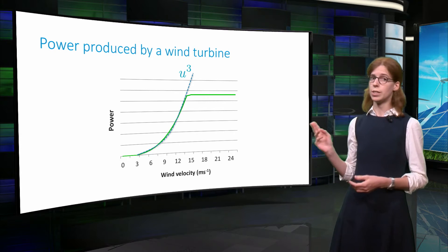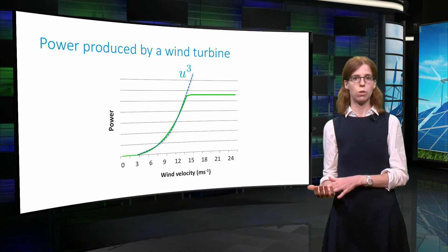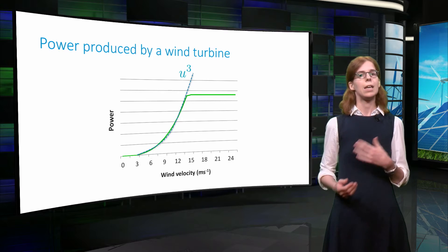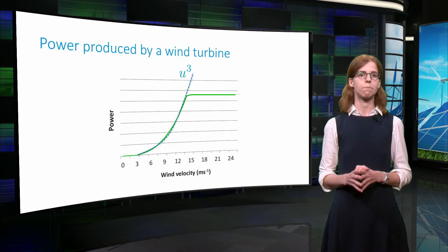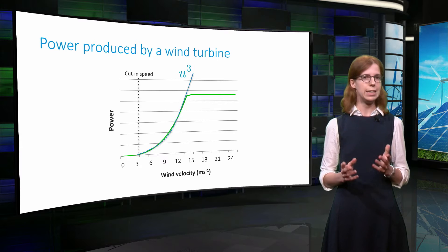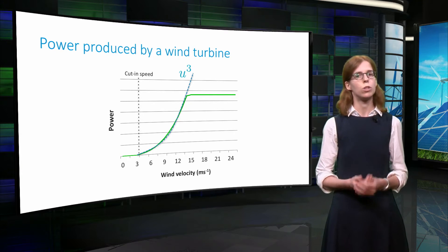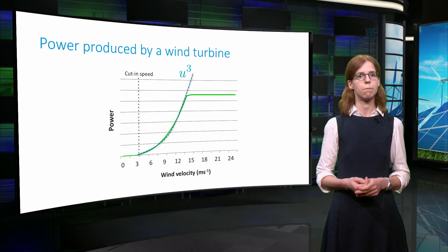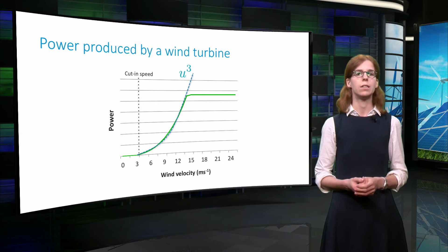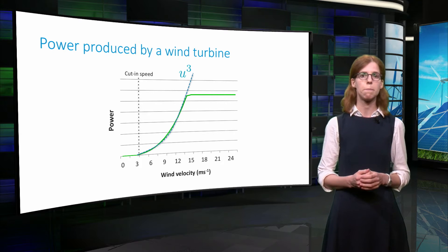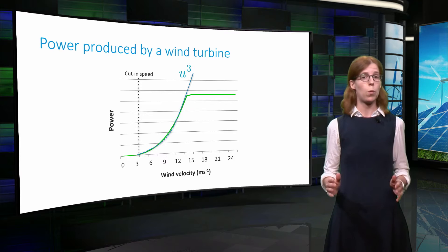This is shown on this plot, which illustrates the power as a function of the wind speed. However, this holds only for a certain range of wind speeds. Indeed, at very small speeds, there is not enough wind for the turbine to actually rotate. The wind speed at which the rotor starts to rotate is called the cut-in speed. Below this value, no power is produced.